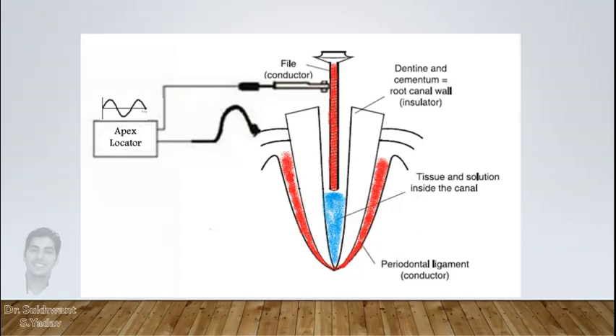When this tooth capacitor is attached to a battery in apex locator, current flows between file and periodontal ligament through irrigant. The flow is opposed by irrigant that is recorded as capacitive reactance.